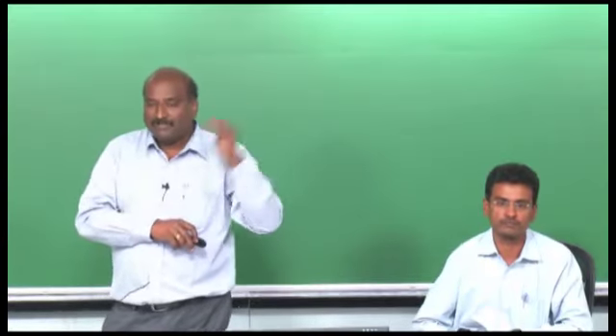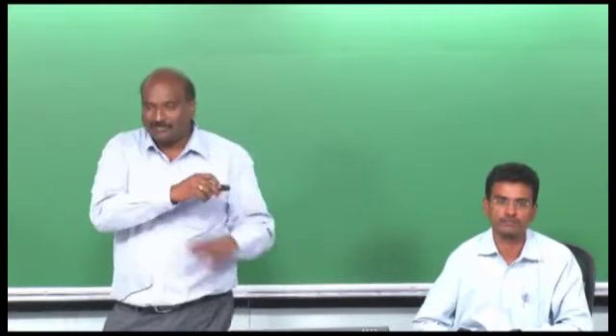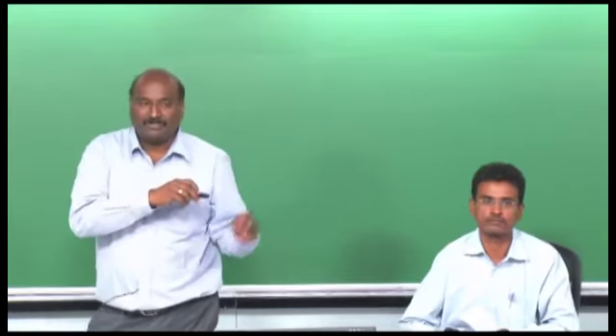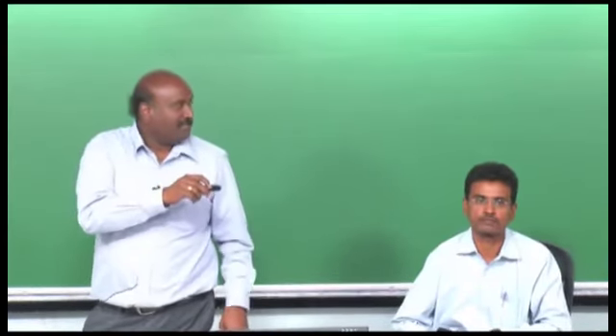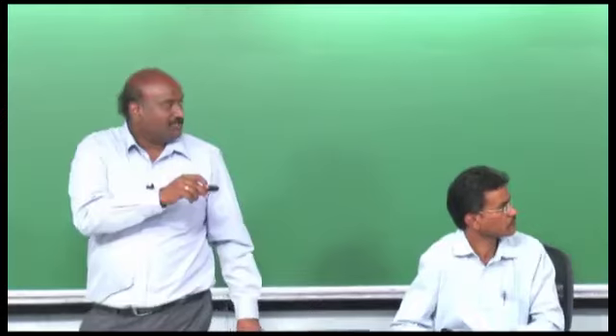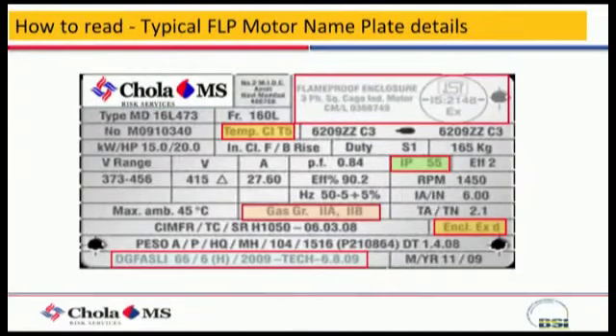If it's a flame proof motor, you'll find details like voltage, amps, efficiency, operating voltage, and ambient temperature, just like on a normal motor. These columns also include temperature class, which varies by motor depending on the application, along with IP class and gas group code, indicating whether it is Ex d.